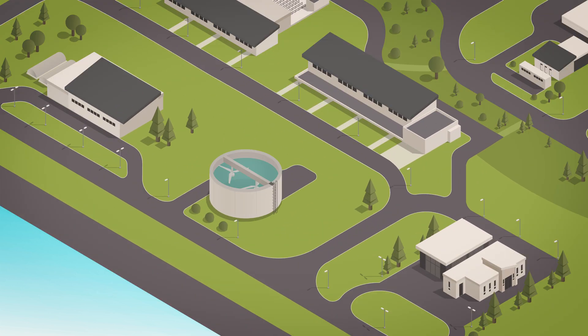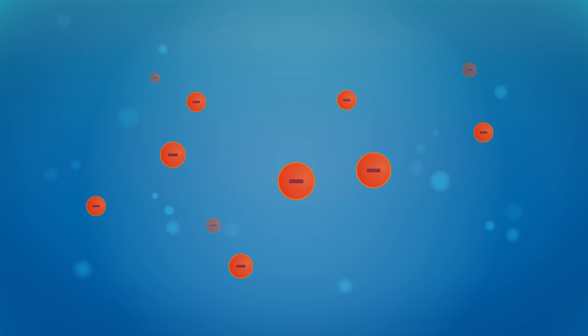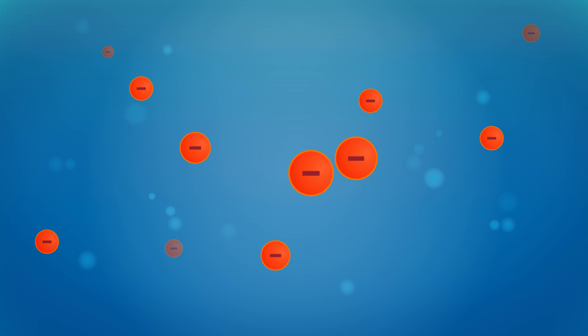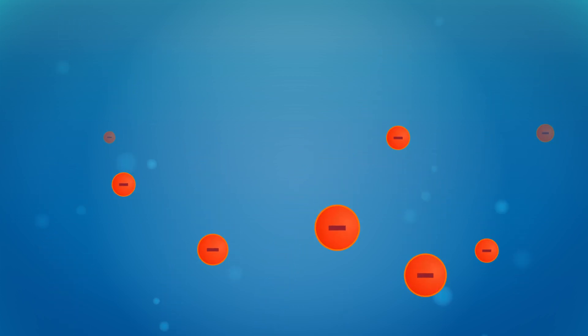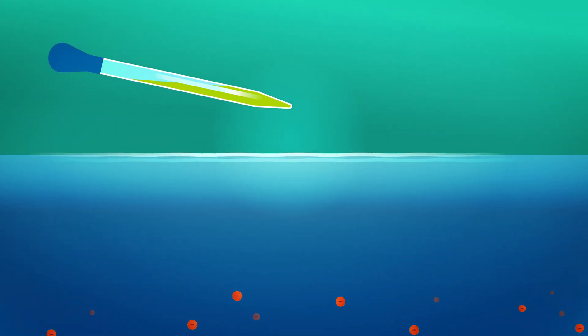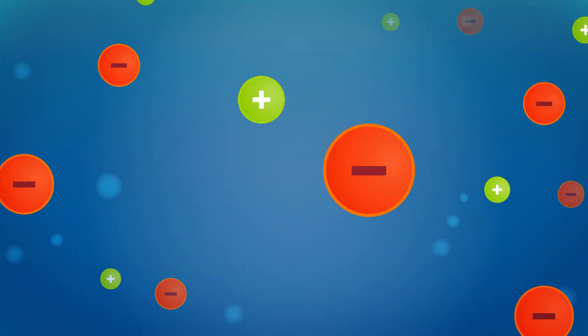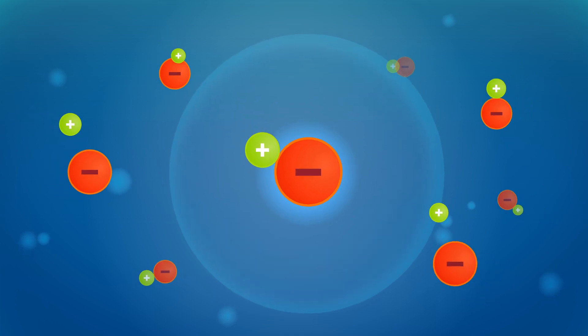Here's what happens inside the coagulation building. There are tiny particles of sediment in the water that have a negative surface charge. When these particles get close, they repel each other just like magnets when you bring the same poles together. By adding positively charged coagulants to the water, a chemical reaction happens that neutralizes the negatively charged particles. A mixing process blends everything and the particles begin to join together.